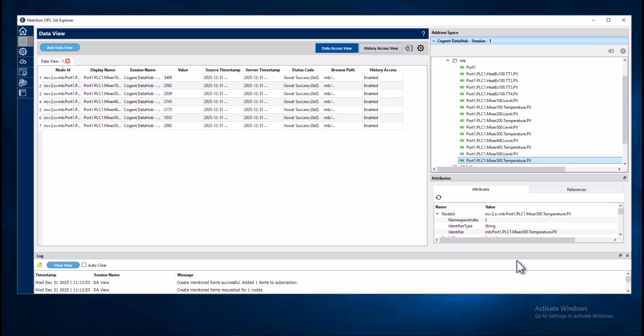So we had a client who wanted to do that. They had some ABCIP drivers already installed from AVEVA. They didn't want to connect to the historian or InTouch or application server. They wanted to get the data directly from the PLC driver, but the client tool they were using only spoke OPC-UA. So this is a workaround where I can put this piece of software in the middle, this Data Hub, and use that to convert DA to UA.